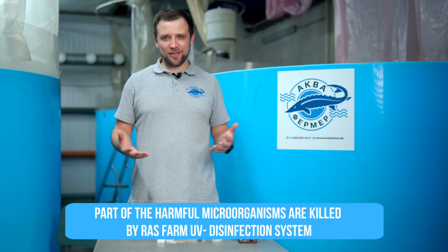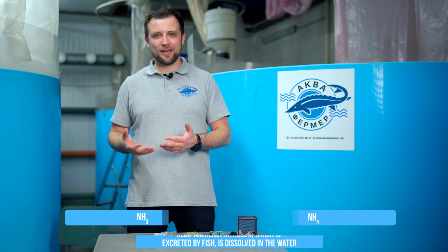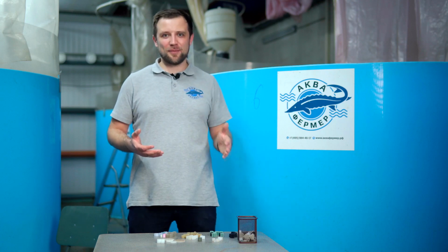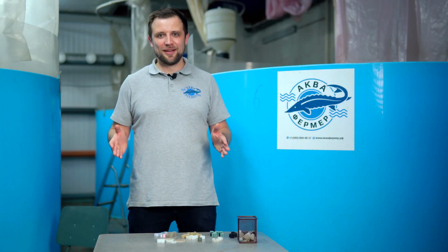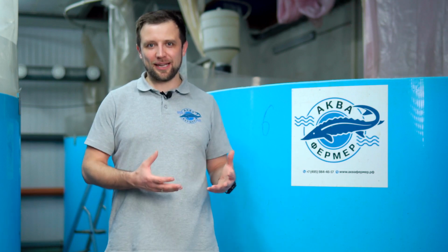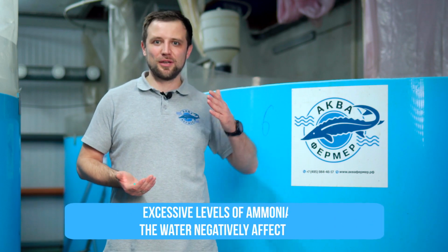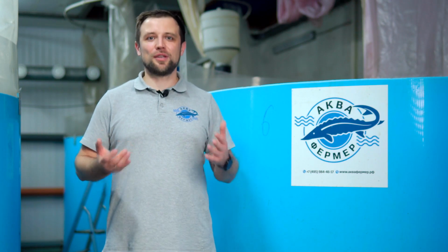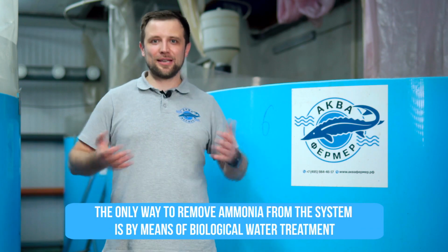And there are also dissolved impurities, actually that's ammonia, NH3 and NH4, which make for the total ammonia nitrogen that fish excretes during its life cycle, usually with urine. It cannot be trapped by either drum filter mesh or ultraviolet disinfection lamps, nor partially by ozonation units. Therefore, the only true and reliable way to treat water from ammonia, which by the way is toxic to fish when exceeding a certain concentration, as fish feels bad and then just dies. That is, RAS can't operate well without it. The only way to remove ammonia from the system is water biological treatment.